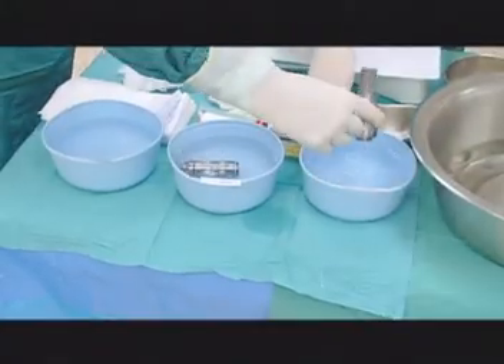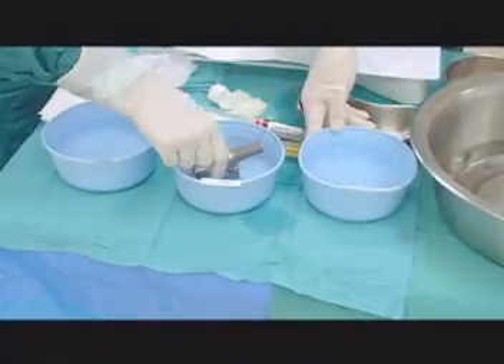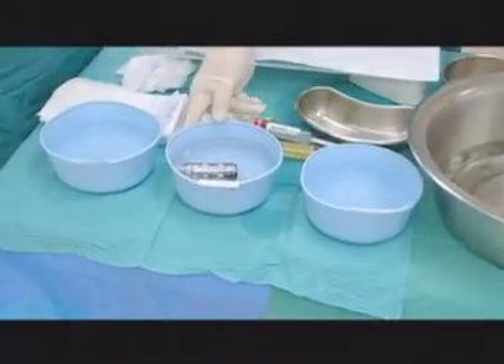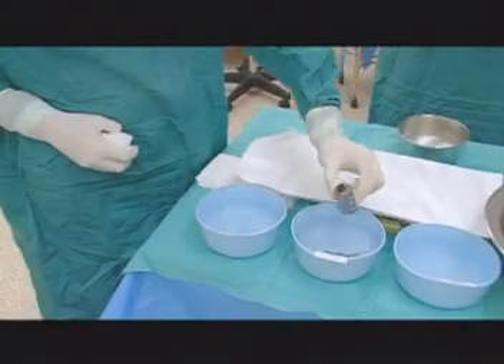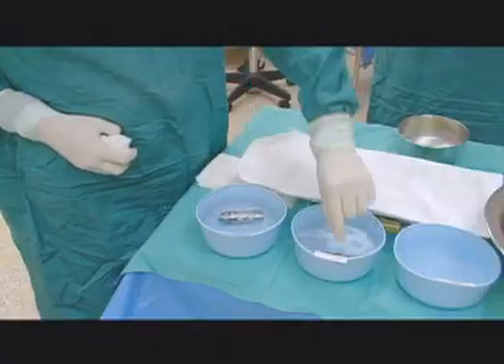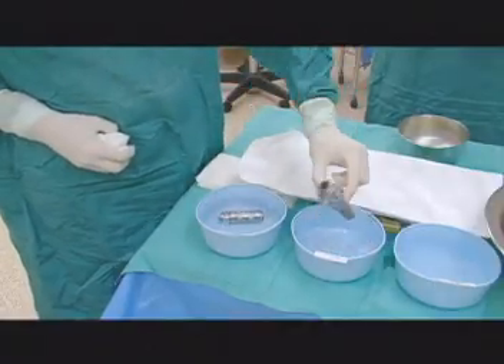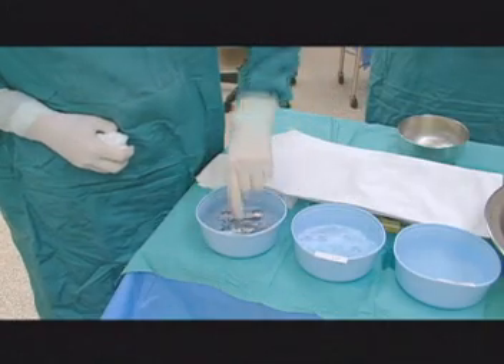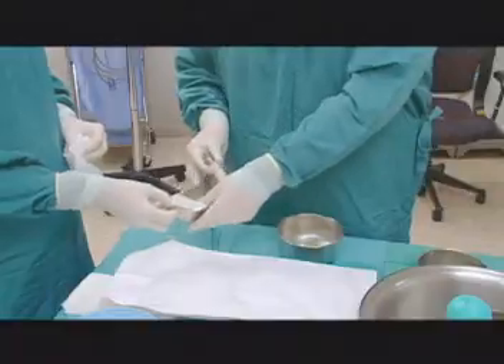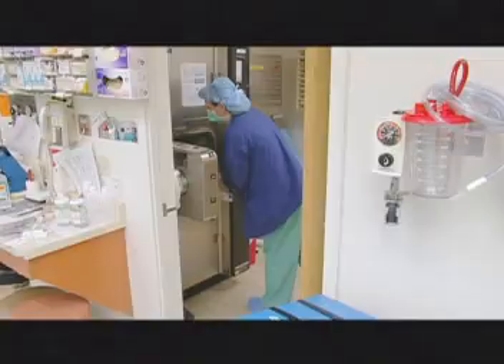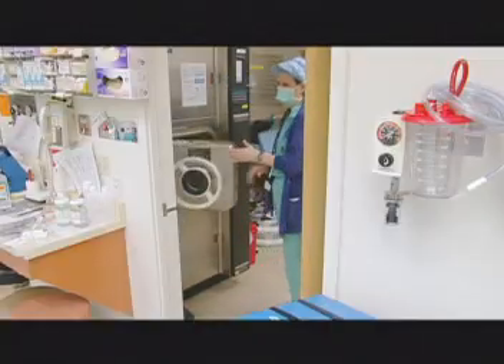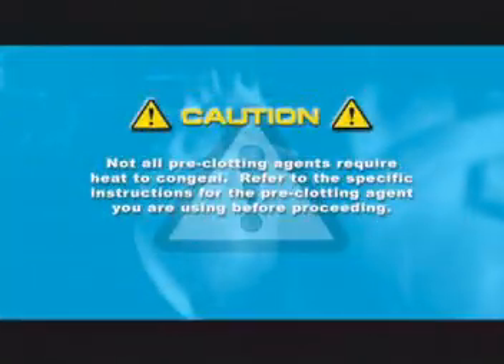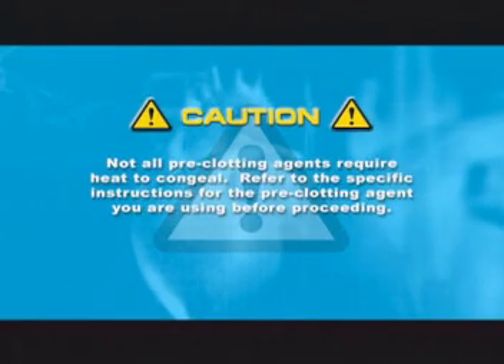After the valve conduits have rinsed for 10 minutes in the first basin, place them into the second basin of saline for 3 minutes, and finally into the third basin of saline for 3 minutes, or until they are ready for pre-clotting. It's important to complete this 10-3-3 rinse cycle. If required, heat the outflow graft in a pre-sterilized pan using an autoclave set at approximately 250 degrees for 3 to 4 minutes. Caution: not all pre-clotting agents require heat to congeal.